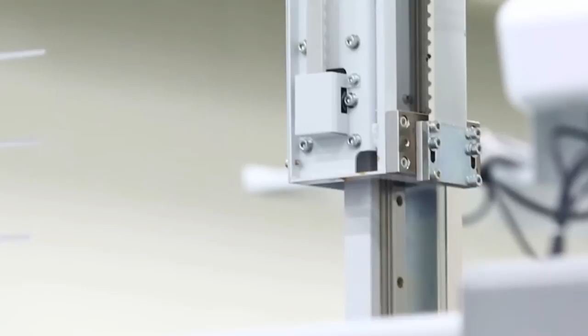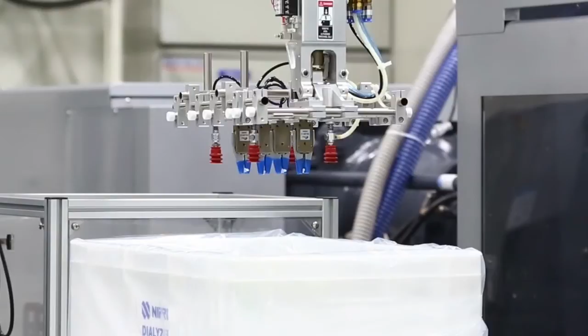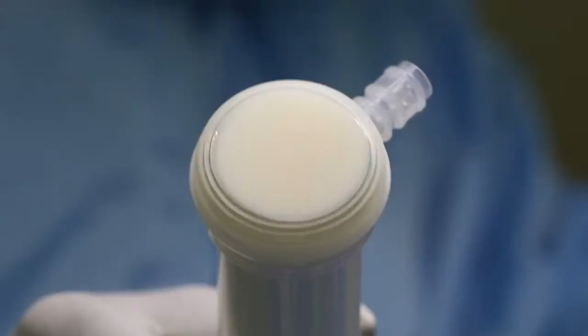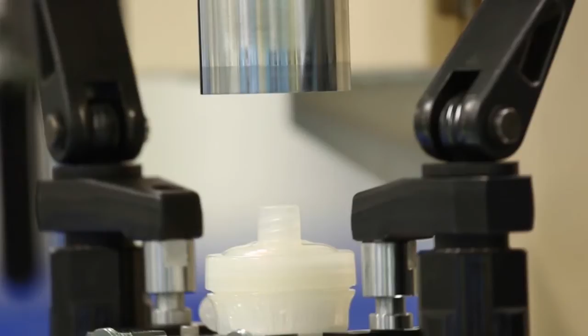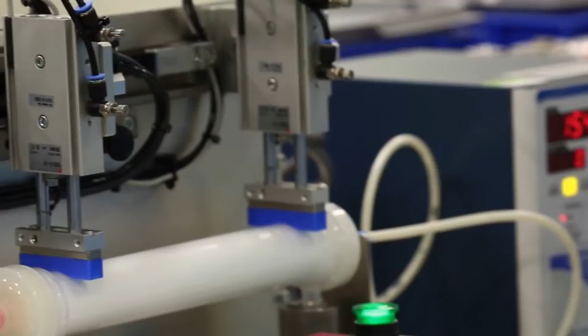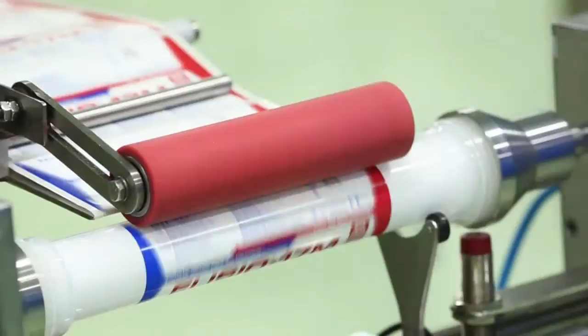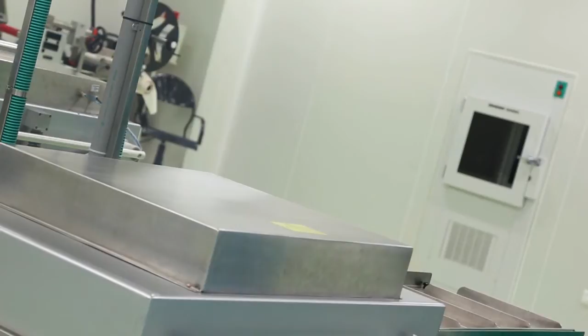The dialyzer casings are manufactured at Nipro's very own in-house molding machines in a clean room environment. The fibers are inserted into the casing, potted with polyurethane, and the ends are cut, giving a mirror-like finish. The caps of the dialyzer are sealed with an ultrasonic cap welding process, making the caps unremovable. Every dialyzer is checked for leakage using ultra-filtered water. The dialyzer is labeled in a labeling machine, then vacuum sealed, boxed, and sent for sterilization.